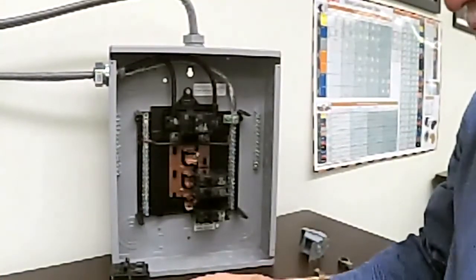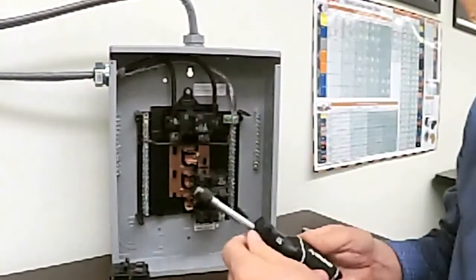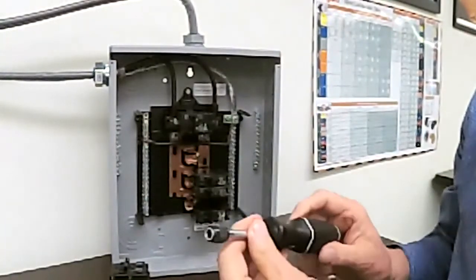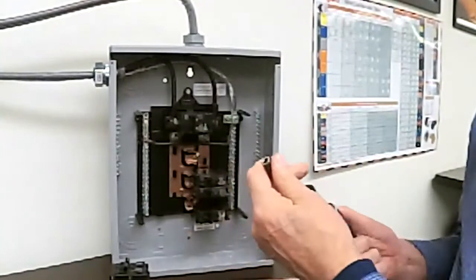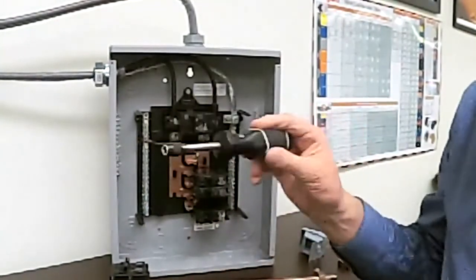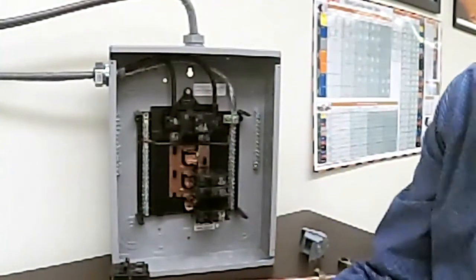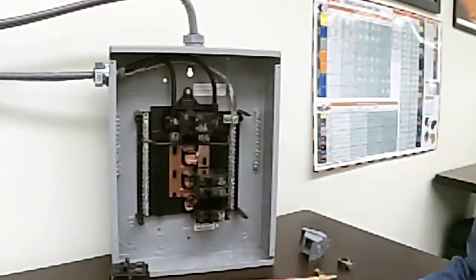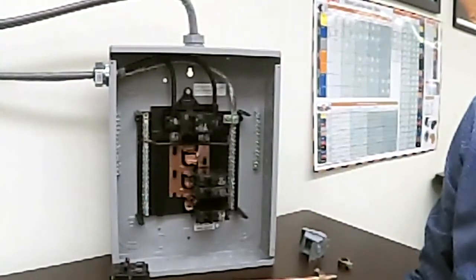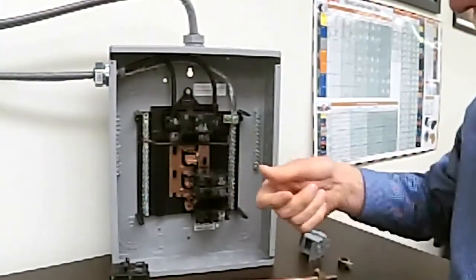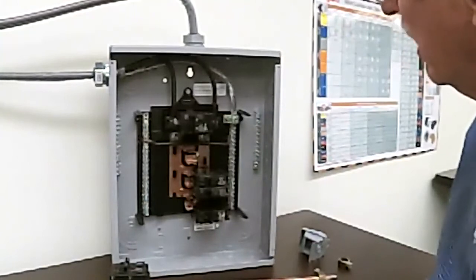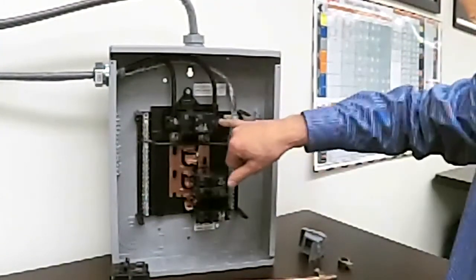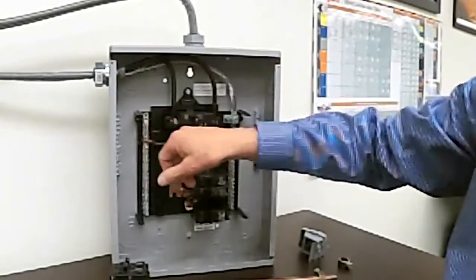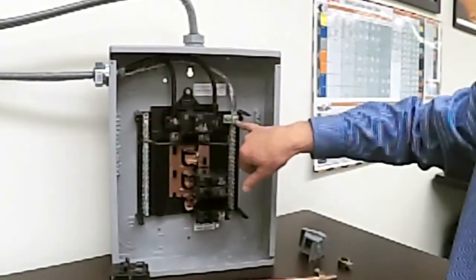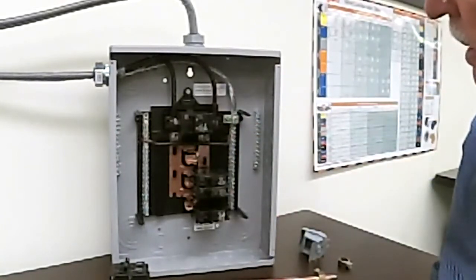This is a torquing screwdriver here. This goes from 0 to 40 inch-pounds. Okay, and another tip, because I had a muscle head in one of my classes that wrecked my torquing screwdriver: the torquing screwdrivers are only for tightening. They're not for loosening. And then the aluminum connections, don't forget, no-ox on the two terminals here and no-ox here on the neutral bar. And I think that pretty much covers it.